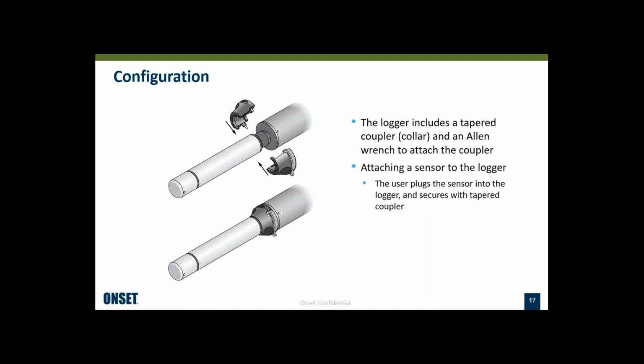To attach the sensors to the loggers, you basically just plug the sensor into the logger. It plugs right in. It has 6 or 7 pins plus an alignment pin, and then you take what we call a collar or a coupler and clamp it around that connection. It holds the sensor to the logger, and then there are 2 screws that the user needs to tighten down to lock that collar in place. There's an Allen wrench they need to use for those screws, and we include that Allen wrench and the coupler with the loggers, so users will have what they need.